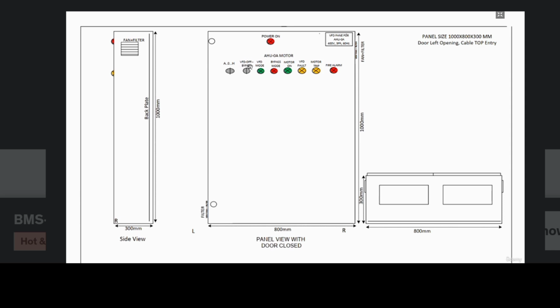Then we have an additional selector switch to select between the VFD and the bypass starter circuit. In normal mode, we will run this AHU in the VFD mode, but if there is any failure on the VFD, we can run this fan in the bypass mode. Then these are the indication lamps showing whether the fan is running in the VFD mode or bypass mode, whether the motor is on, or if there is any fault on the VFD or motor trip, or if there is any fire alarm signal, an indication is provided here.